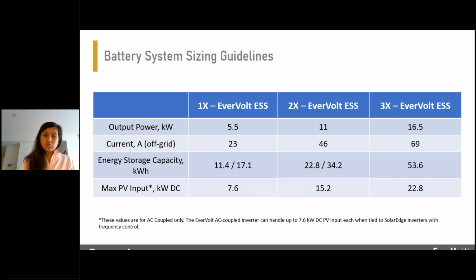And if the customer wants more storage capacity or more hours of backup, then they would be required to add additional battery cabinets. You can see with a single Evervolt, we can go as high as 17.1 kilowatt hours. Actually, you can also stack up to 2 battery cabinets for a capacity of 34 kilowatt hours per system. Similarly, if you stack multiple systems, the largest size you can obtain is up to 3 Evervolt inverters connected, which would equate to 16.5 kilowatts of output power. And if each of the inverters is connected to 2 battery cabinets, that would mean 34 times 3, so as high as 102 kilowatt hour capacity.